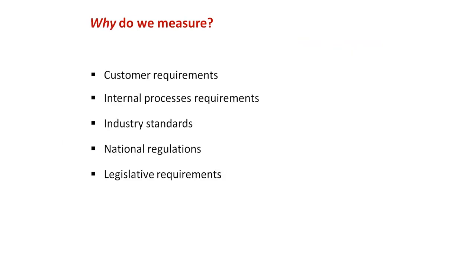Why do we measure? It could be that our customers require that we make that measurement. They have their own specifications. For certain processes in manufacturing, it could be an internal requirement, for instance, in a bottle of soft drink, the level of brix or pressure in there. So it could be a requirement for your internal processes. When we do the gas stations every 6 months or twice a year, it's a legal requirement. Measuring instruments used for trade have to be verified according to our Metrology Act at least twice a year or once a year. So it's a legal requirement. So there are different reasons why we measure.